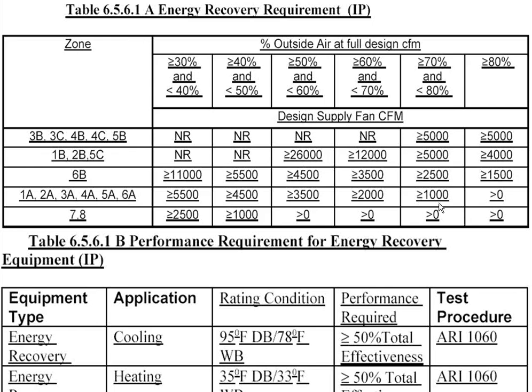Similarly, if you go up, you have 1,000 CFM in your system, and you're using between 70 and 80% outside air in that system, so that's almost 100% outside air. Then you have the requirement for an energy recovery ventilator. If you look at some of the other climates, these are the dry coastal climates and the western climates. They don't have that humidity requirement at those smaller CFM levels, so they're actually not requiring that.